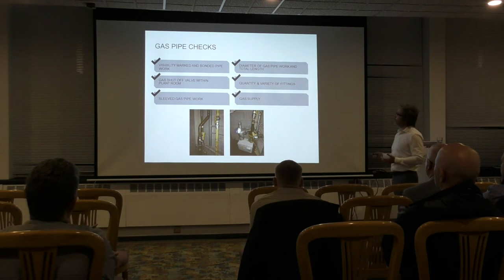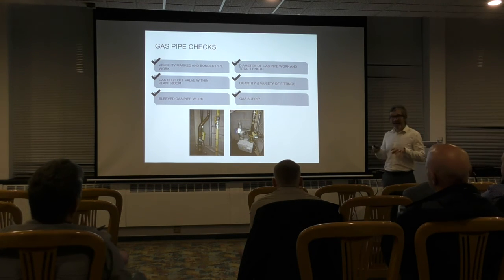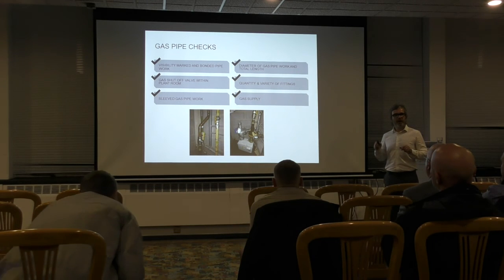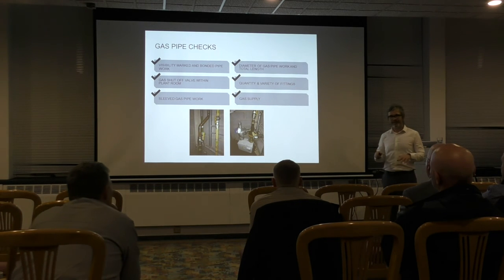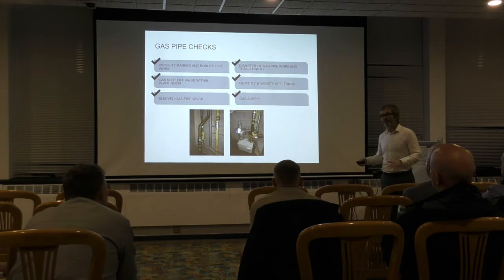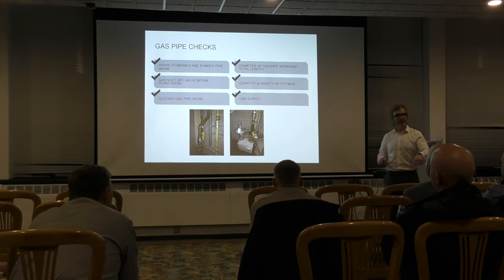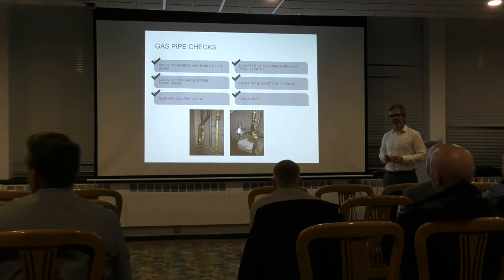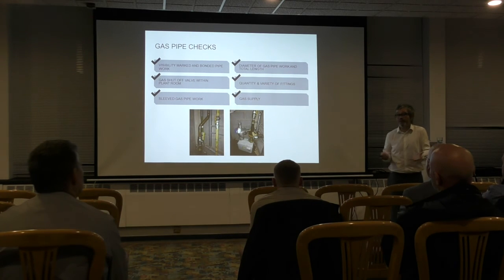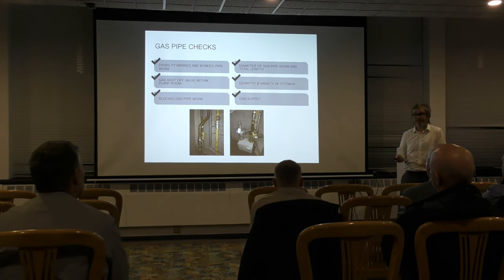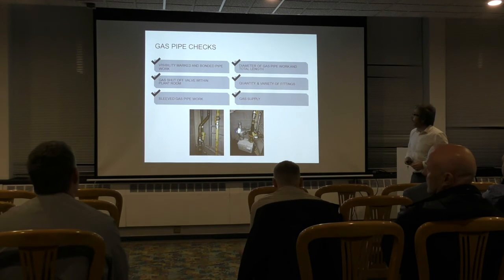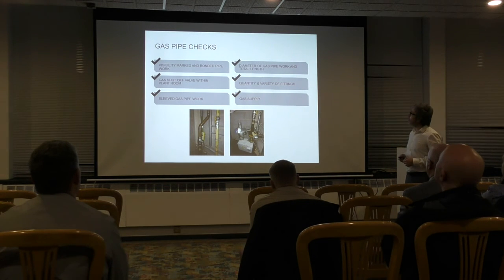Is it visibly marked and bonded where necessary? Is there a gas shut-off valve in the plant room? Now, I always thought it was mandatory. You had to have a gas shut-off valve in the plant room. And somebody argued this the other week and said, well, actually, no, you don't need it in the plant room. There needs to be one outside the building. That's the mandatory side. It's just a recommendation to have it in the plant room. But if it's a recommendation, I would say it's good practice to do so. Where it's sleeved where necessary.